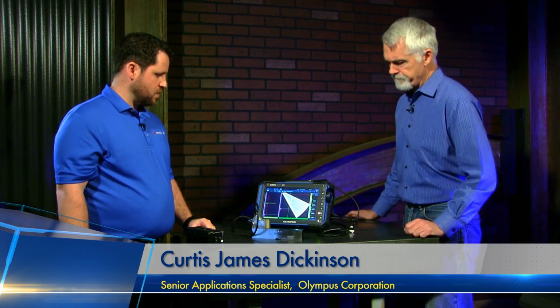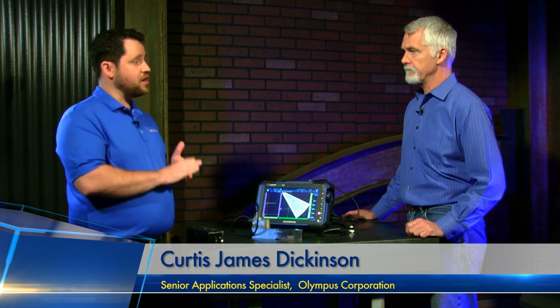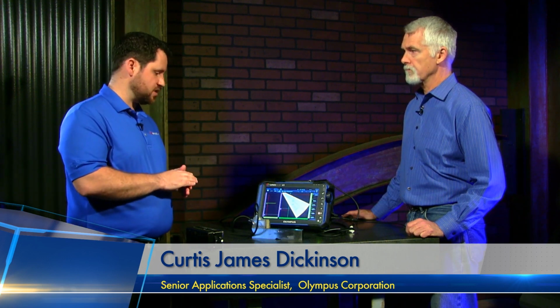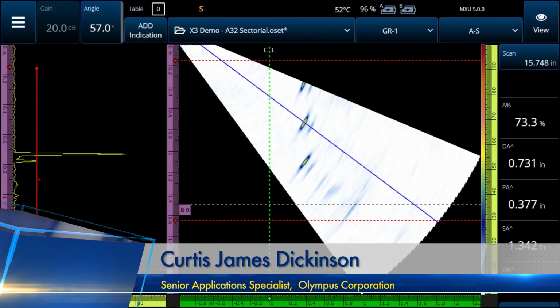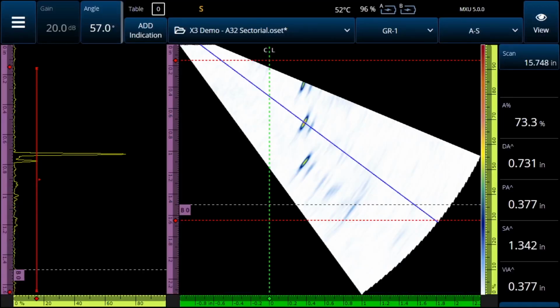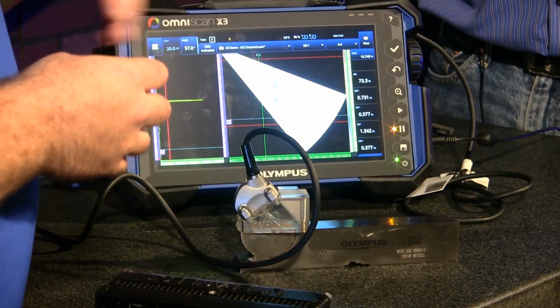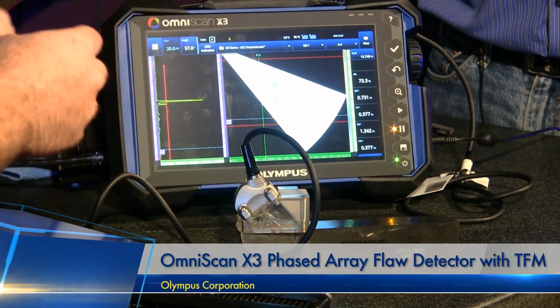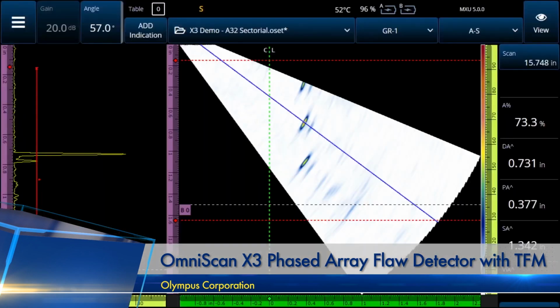So take us through the operation. Yes. So in addition to the overall box design, we also try to make a lot of software improvements in addition to a lot of hardware improvements to the system. What you're seeing on the front here is a basic phased array setup for the instrument. On the display here, we have a sectorial scan on the S-scan display alongside the analog A-scan display. So this is a very traditional type of phased array inspection that you'd see on this type of unit. We're inspecting from 40 degrees to 70 degrees with the blue line running through the display here being our toggle for the A-scan display. Okay.